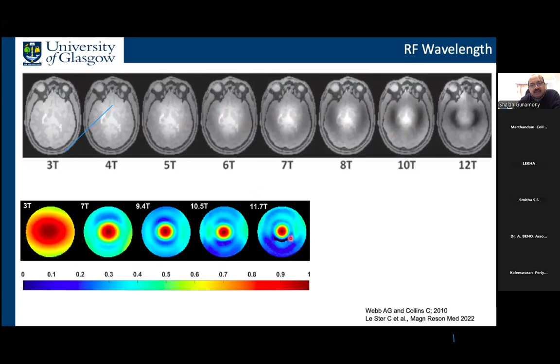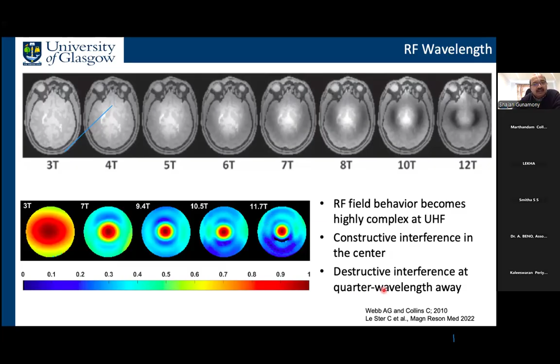That's because the RF field behavior becomes highly complex at ultra high field. There is constructive interference in the center, and then destructive interference in the periphery, which is about a quarter wavelength away from the center. You see these dark rings. So for example, at 11.7 Tesla, because the wavelength is so short, you see 2 of these dark rings because of this quarter wavelength, which is quite short at that frequency.